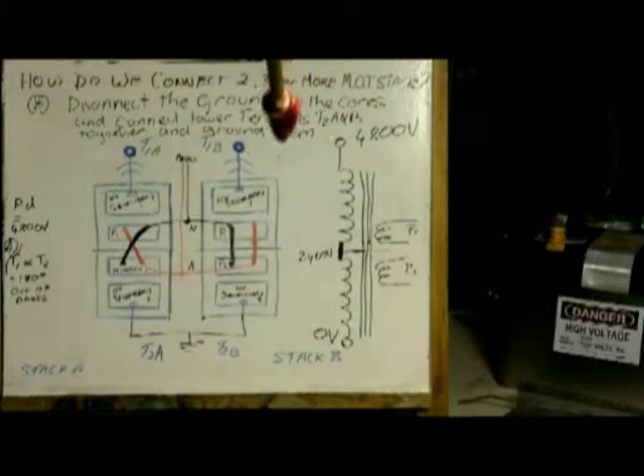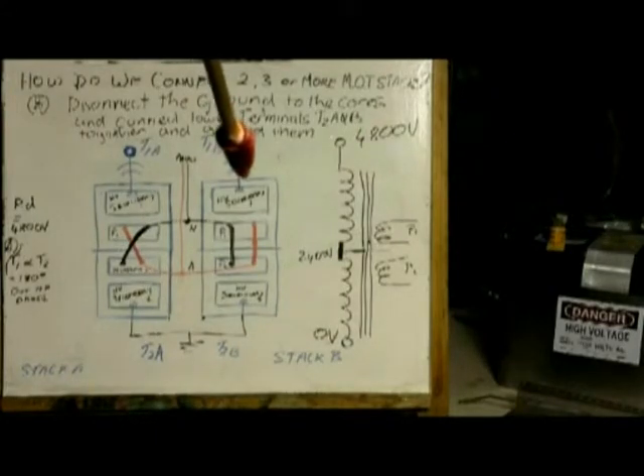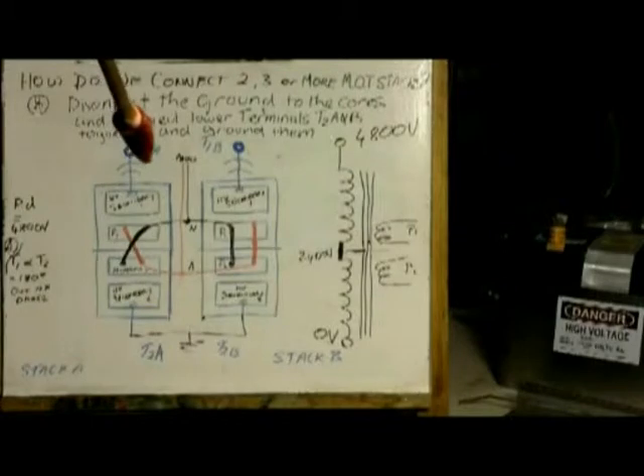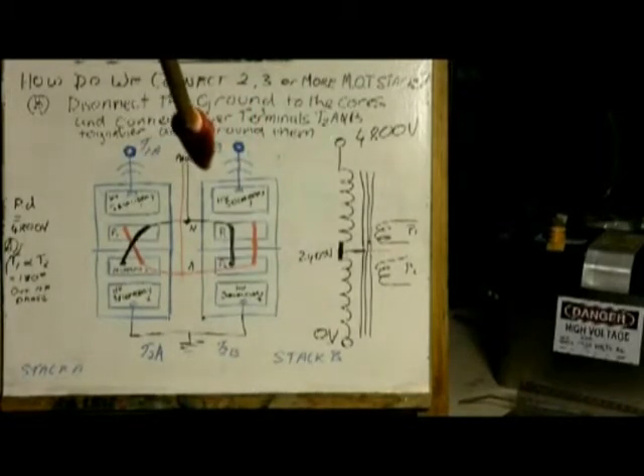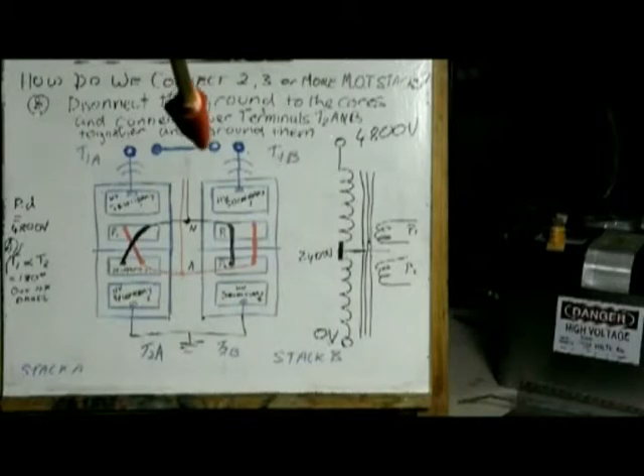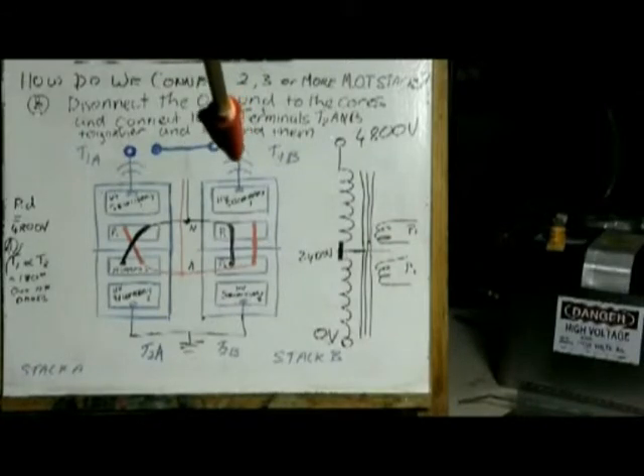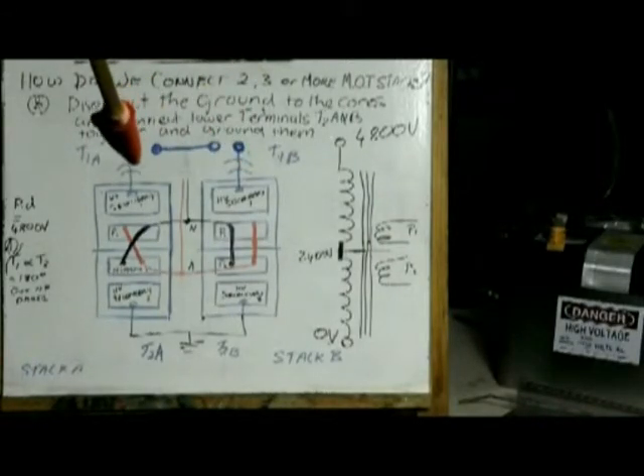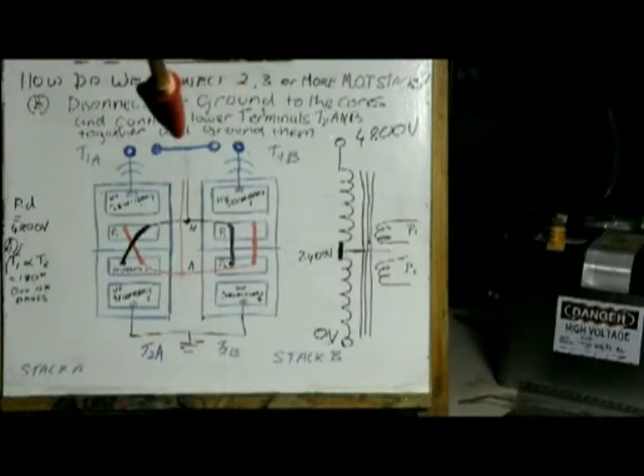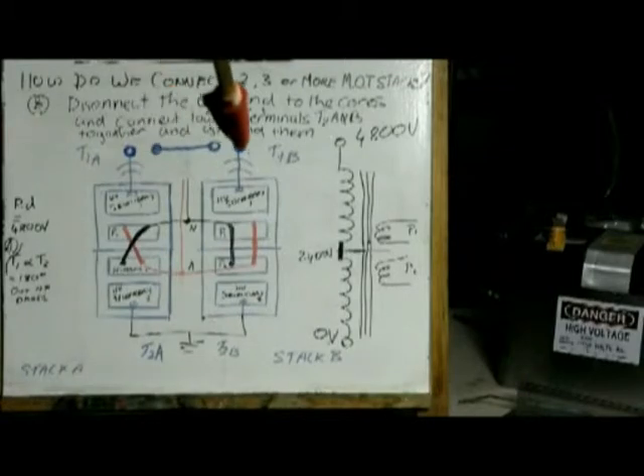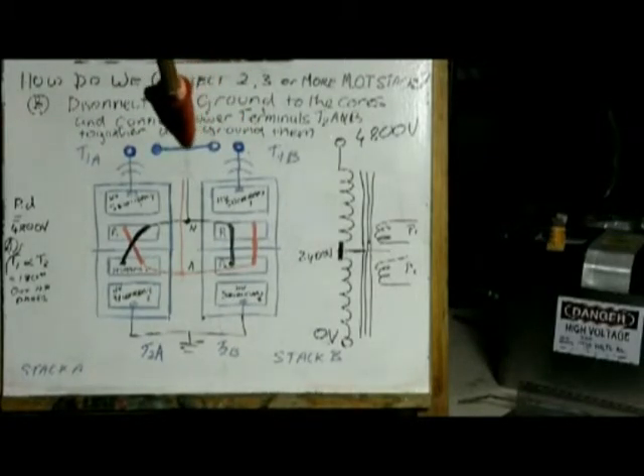Okay, so now you check the terminals T1A and T1B, and you find that you definitely do have 4800 volts on each terminal. You switch the unit on, and what happens? You even bring a metallic rod to the terminals. 4800 volts per terminal. You should have a total of 9600 volts now between both. So you're looking for a discharge between both of these. Everything's looking good.